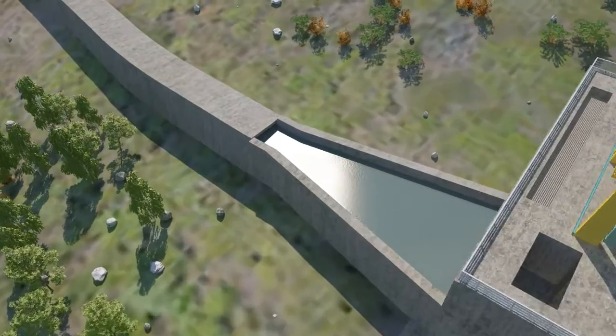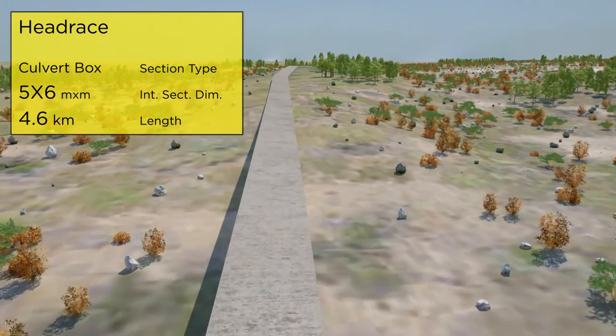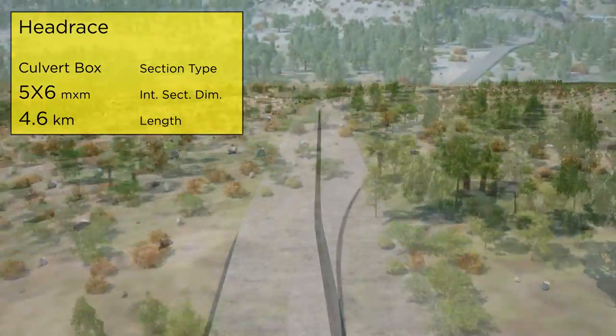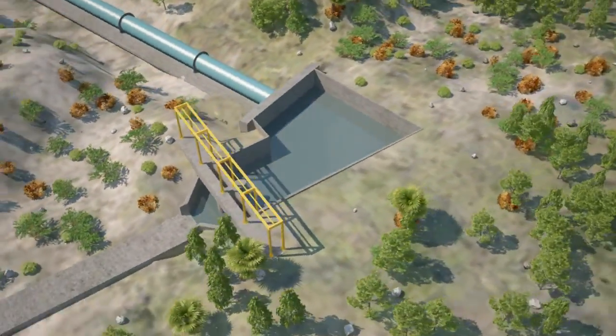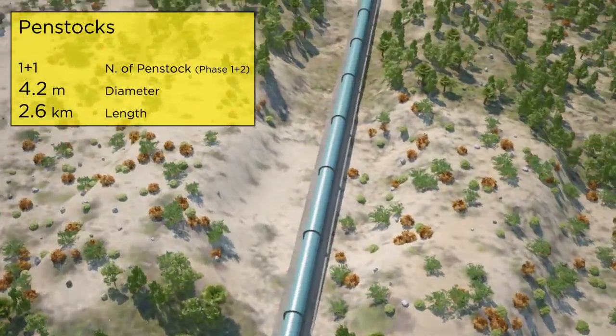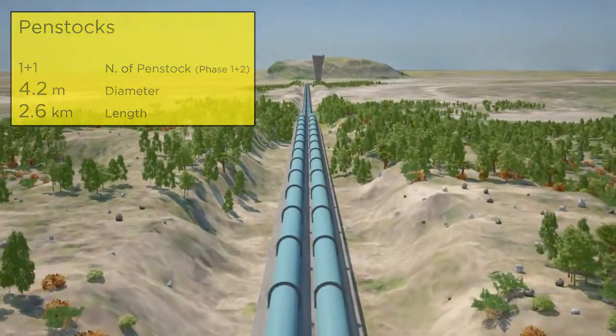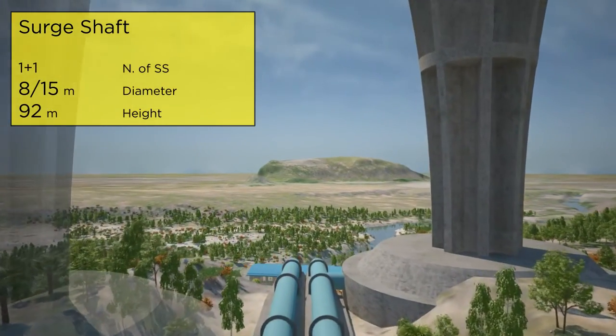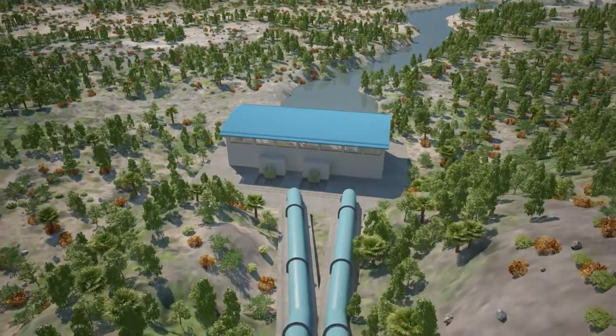The waterways from the reservoir to the powerhouse will include a culvert box channel 4.6 kilometers long, which will be doubled during the second phase, a head pond, a 2.6 kilometer long penstock with a diameter of 4.2 meters, a surge shaft with an 8 to 15 meter diameter, and finally the Lufubu 1 powerhouse.